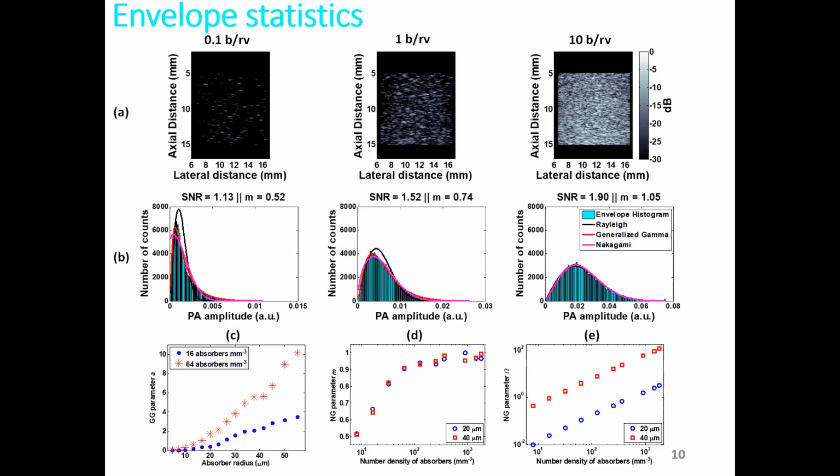So to answer your question, the bead phantoms are good in order to retrieve the frequency response of your system, making the assumption, which is not a terribly bad assumption, that you have a large number of absorbers within your resolution volume, and at the same time, the sizes of these beads reflect whatever it is that you are studying, such as tumors.